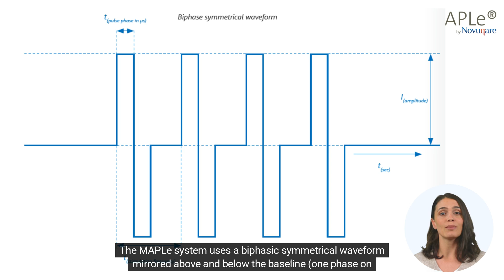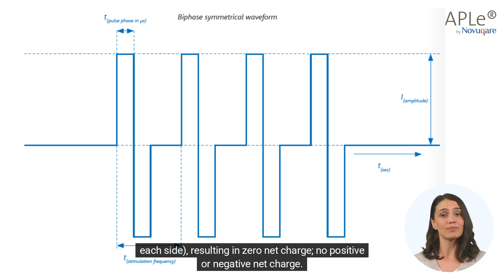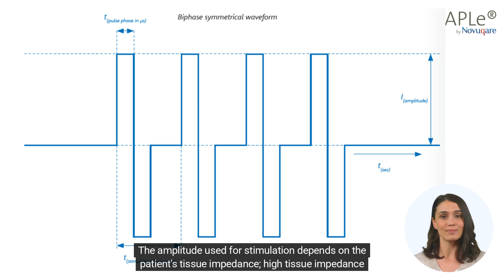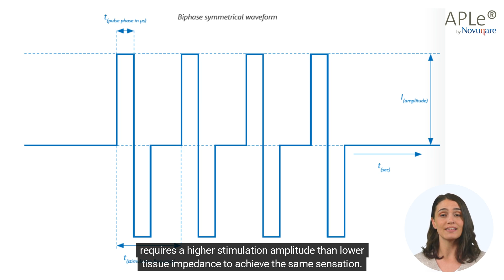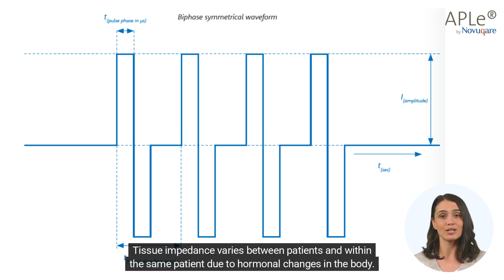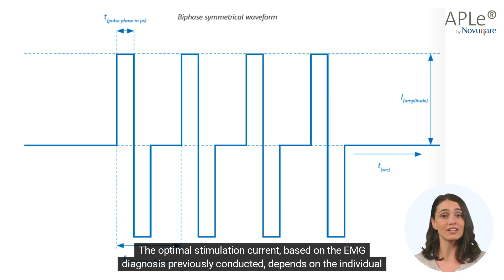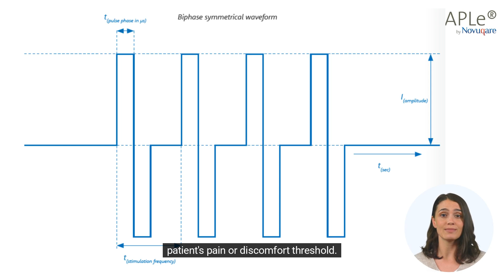Stimulation current parameters. The MAPLe system uses a biphasic symmetrical waveform mirrored above and below the baseline, one phase on each side, resulting in zero net charge, no positive or negative net charge. The amplitude used for stimulation depends on the patient's tissue impedance. High tissue impedance requires a higher stimulation amplitude than lower tissue impedance to achieve the same sensation. Tissue impedance varies between patients and within the same patient due to hormonal changes in the body. The optimal stimulation current, based on the EMG diagnosis previously conducted, depends on the individual patient's pain or discomfort threshold.